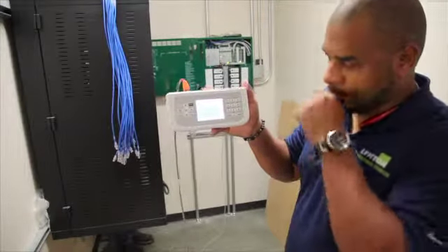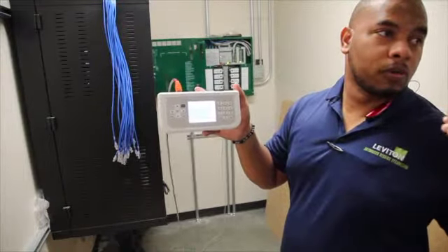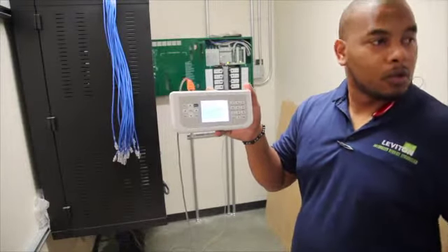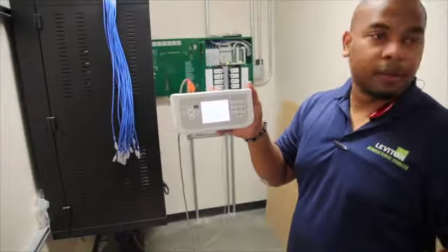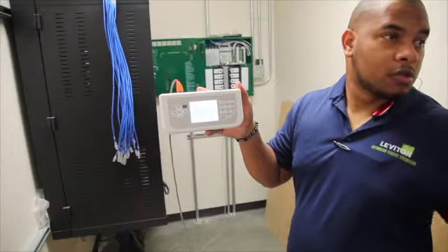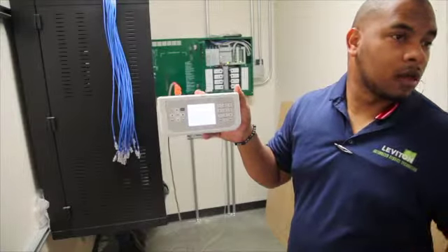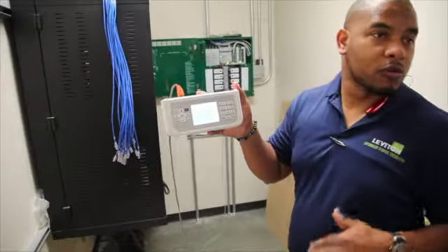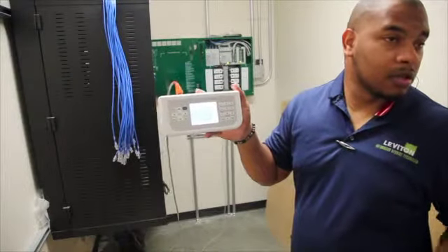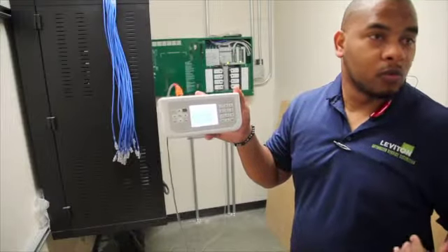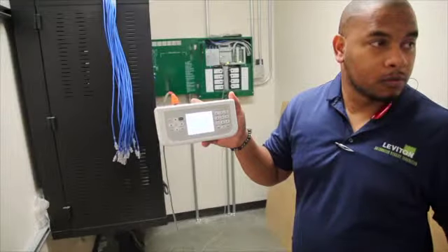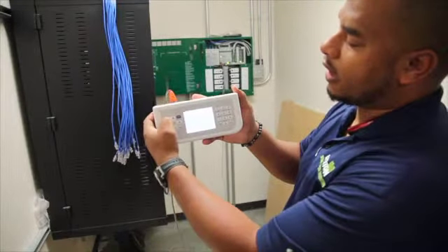So when you walk in the space, the occupancy sensor, if the photocell allows, will turn the lights on, and then you have the capability of going to the digital switch to override the occupancy sensor by turning the lights off or turning them back on. This is the only instance you have for this schedule, so there's really no reason for you to change it unless you wanted to incorporate a hard off, which you really don't have to because you have occupancy sensors. Follow? Okay. So if I hit escape, I can look at my exterior schedule.